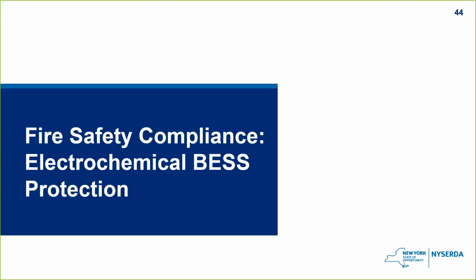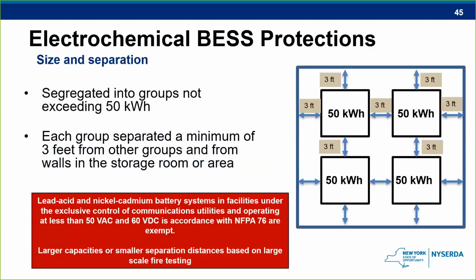All right, so we're going to get into some more of the specific requirements. And these are based on the type of system that we're talking about and also the location of the system, which we'll get into in a little bit. So first, we have a size and separation requirement. Grouping of energy storage systems to a maximum of 50 kilowatt hours is there to reduce the fire load of any one group or rack. This grouping does not apply to remote outdoor installations. We'll see that a little bit later. It does, however, apply to walk-in containers or cabinets that are outdoor and near other exposures.